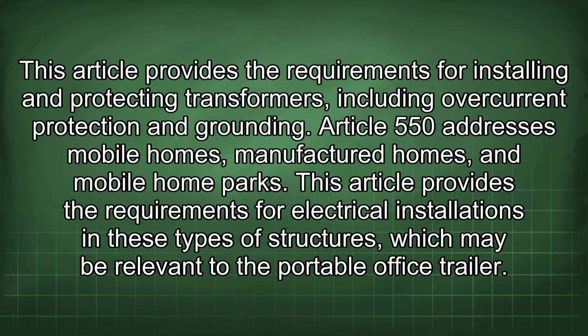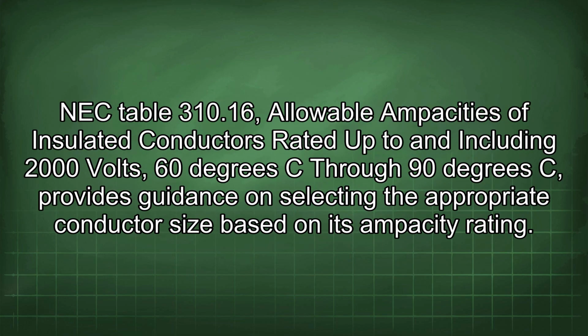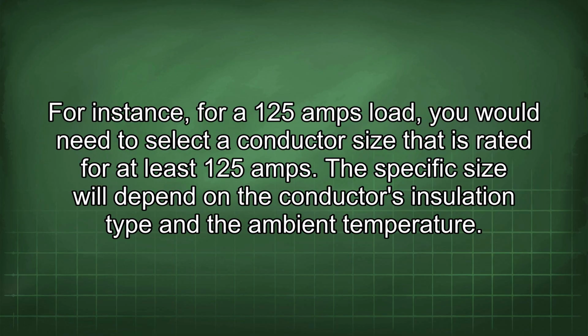Article 550 addresses mobile homes, manufactured homes, and mobile home parks. This article provides the requirements for electrical installations in these types of structures, which may be relevant to the portable office trailer. NEC Table 310.16, allowable ampacities of insulated conductors rated up to and including 2000 volts, 60 degrees C through 90 degrees C, provides guidance on selecting the appropriate conductor size based on its ampacity rating. For instance, for a 125 amps load, you would need to select the conductor size that is rated for at least 125 amps. The specific size will depend on the conductor's insulation type and the ambient temperature.